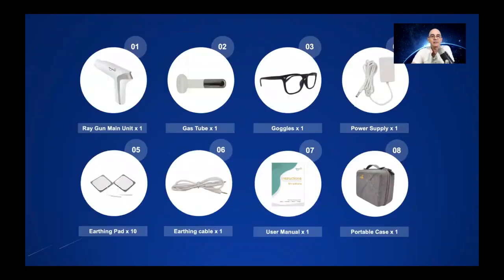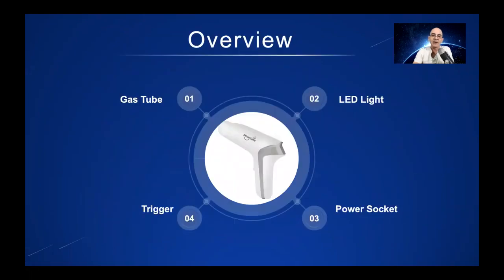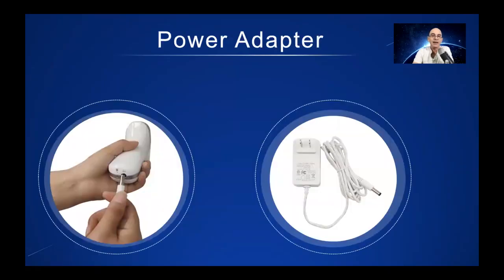You get the main unit, you get a gas tube. The gas tube is replaceable. You can easily remove the gas tube, which is this, and replace it if you need to. You have goggles, power supply, the earthing pad, earthing cable, a user manual, and a beautiful portable case. There's an LED light on the handle. That lights up to say that the ray gun has power and is ready to run. The power adapter, you just plug into the base near the handle. We have adapters for all different countries, so don't worry if your power adapters look different in your part of town. We'll send one that's appropriate to where you live.